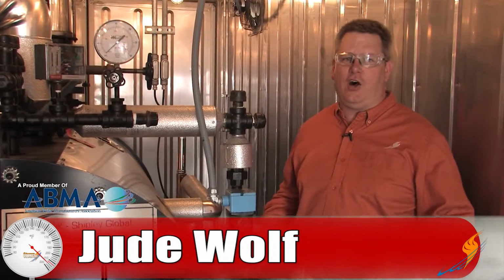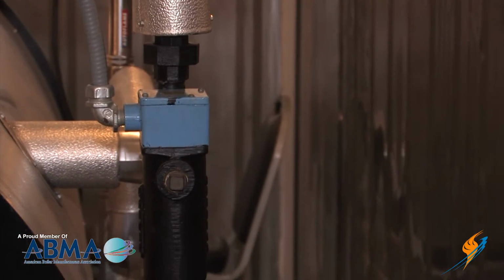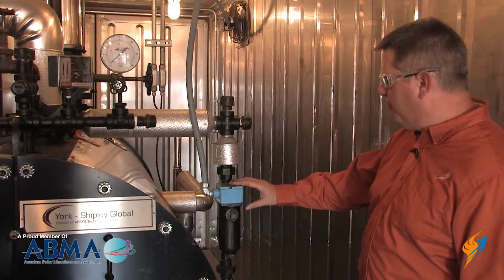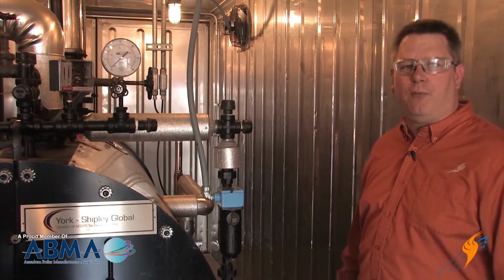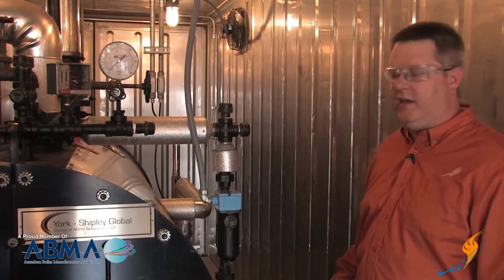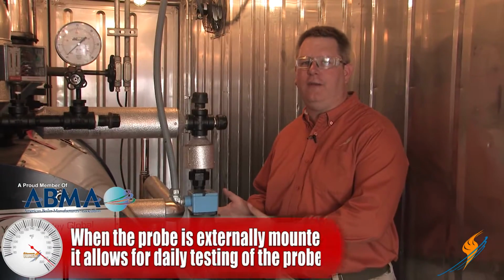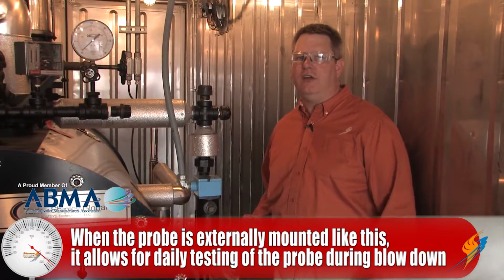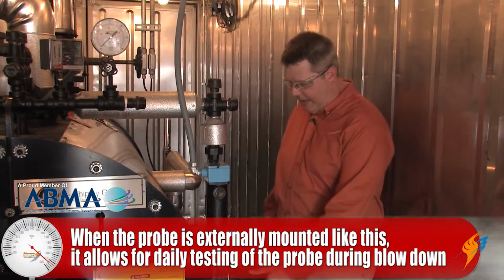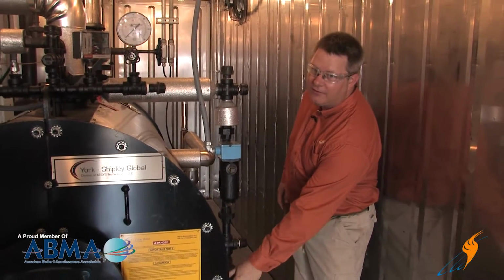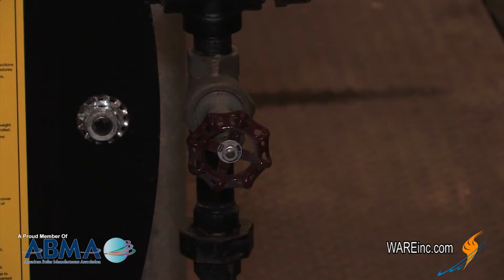Primary and low water cutoff devices are arguably the most important safeties on a boiler, because if we don't have water in the boiler, it's going to be rapidly destroyed by the temperature of combustion. This is an example of a secondary low water cutoff probe housing, and we'll be talking about probe type low water cutoffs today. One advantage of using an externally mounted secondary low water cutoff, even if it's a probe type, is that it allows us to daily blow down and test operation of the safety.